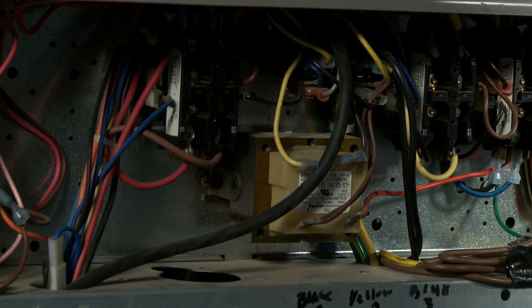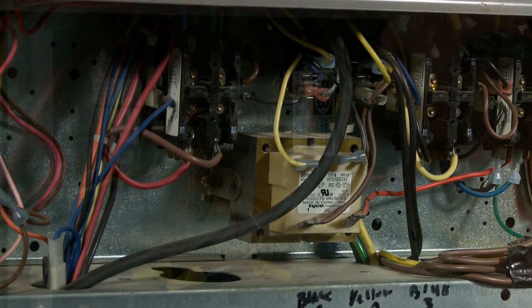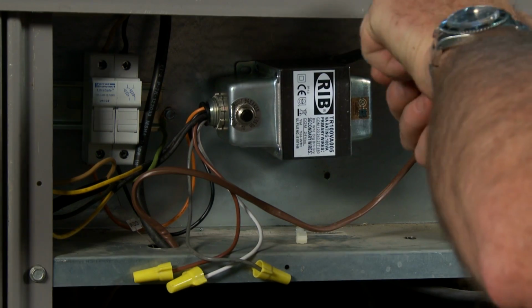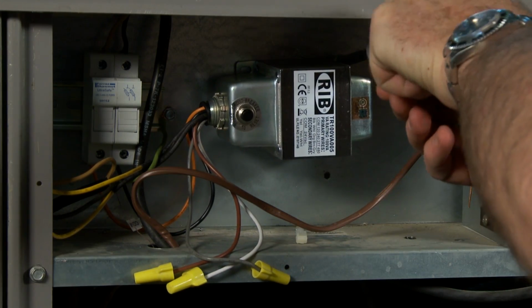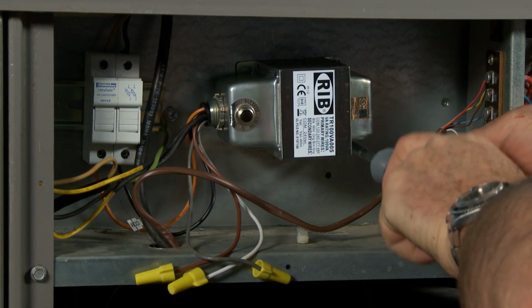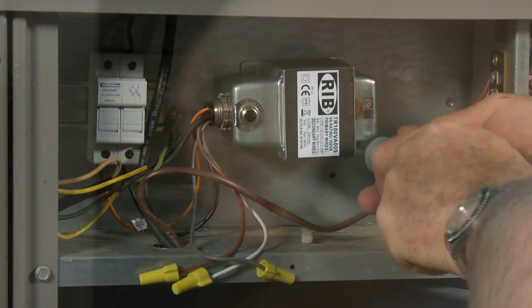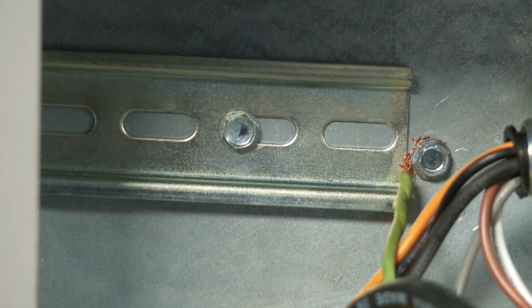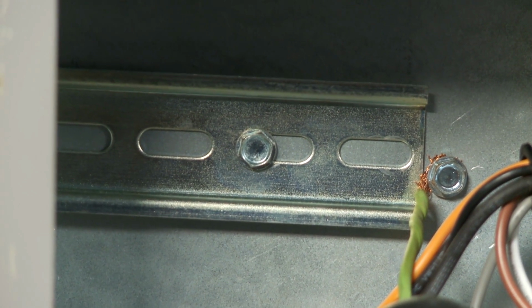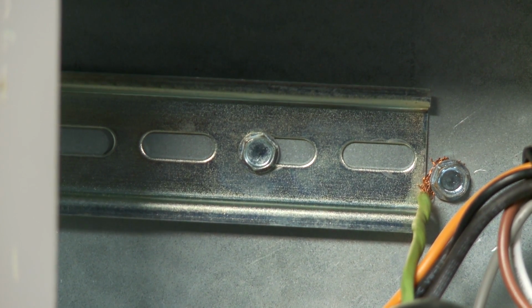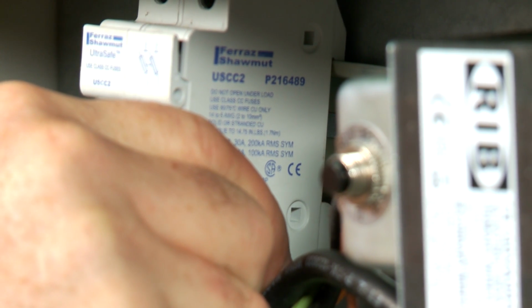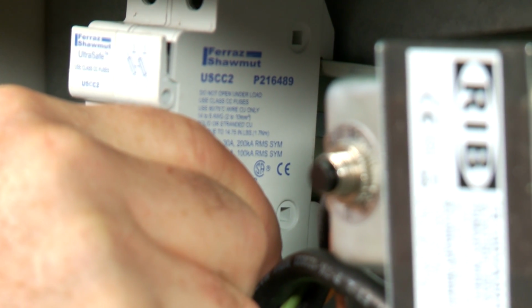Now, open the control cabinet of the outdoor unit. Take the 24-volt transformer shipped with your system and securely mount it using field-supplied sheet metal screws in an area that won't cause interference with any operating equipment in the cabinet. Locate an area within 6 inches of the transformer to mount the included DIN rail using field-supplied sheet metal screws. Snap the fuse block into place on the DIN rail.